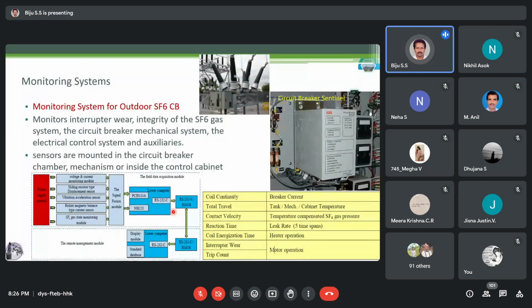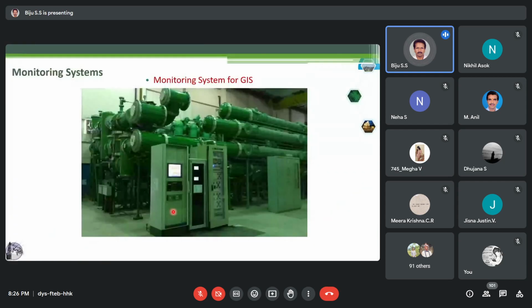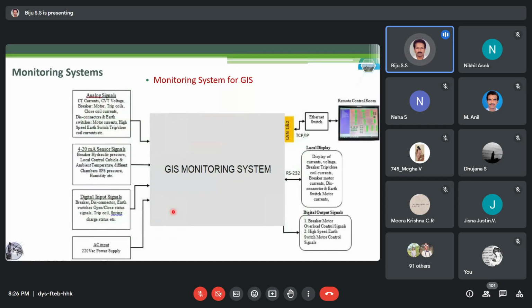This is actually a schematic diagram of the system. Then you have the GIS monitoring again. I'm just talking about various monitoring systems available nowadays. Again, here also, all the parameters will be like current, voltage, motor current, trip coil, closing coil currents, switch current, switch disconnector current, switch currents. I mean, those things will be monitored.